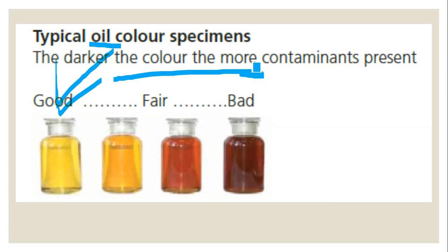Now let us understand why the BDV test - breakdown voltage test - is being done on transformer oil. As already told, when moisture or some other foreign material is absorbed by the transformer oil, its insulation capacity comes down. That has to be tested, and that test is known as the breakdown voltage test.